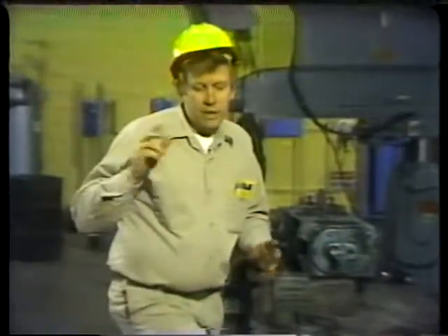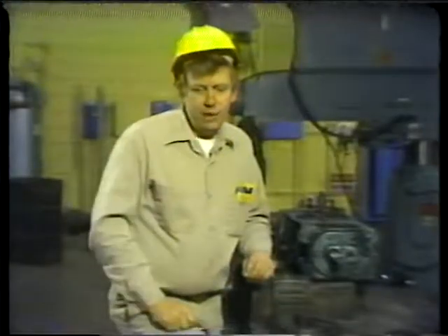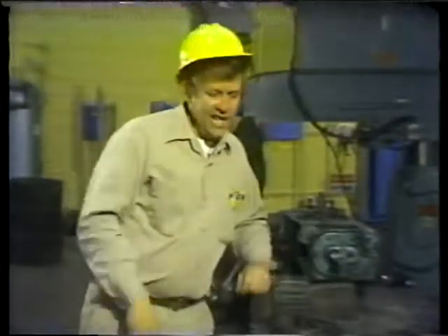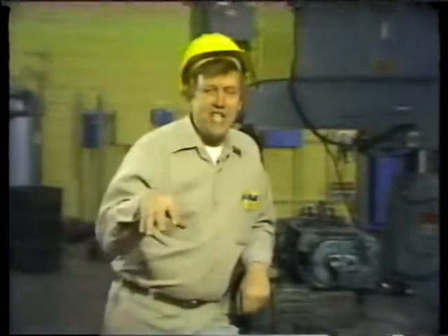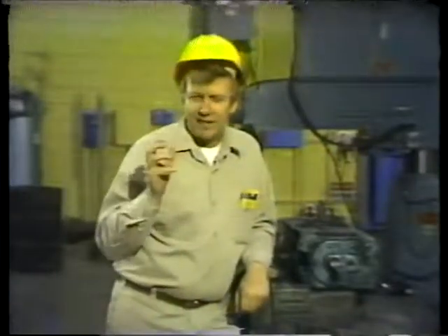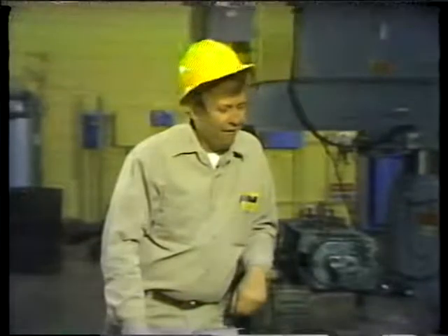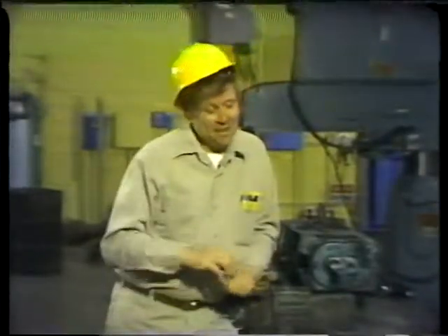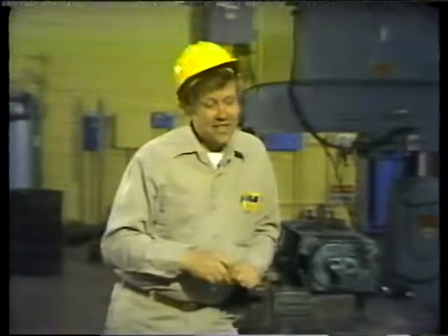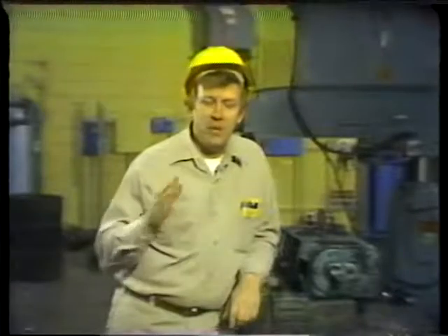So I'm standing there, my supervisor, he got the work permit, had it in his hand, so we popped the doors off of there. I'm getting ready to get inside it when I hear something click, and I hear it start to whine. So I backed away from it. Man, this fan just took right off. 600 RPMs, man, she turns up a little speed. It scared me good, because if I'd have been inside there, she'd have just chewed me right up. There wasn't no way in the world I could have stayed away from those blades.